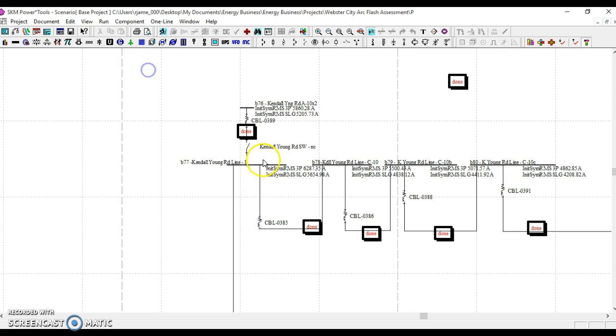Okay, now we want to do a data block format, which is essentially what prints out to the model, and there we are. You see that a three-phase fault condition would result in just over 6,000 amps, and a single-line and ground fault would result in roughly 5,600 amps.